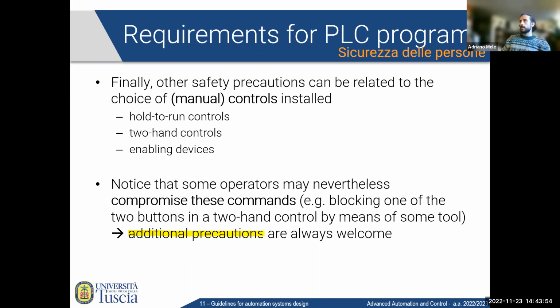But maybe you also want to check that the two buttons are pressed within a specific time interval—pressed together, or at least not more than 1 second apart. Because if someone takes a tool, locks one button, then moves to the other side and presses the second, probably more than 1 second will pass. In that case, you know something is wrong and you don't operate the machine anyway.